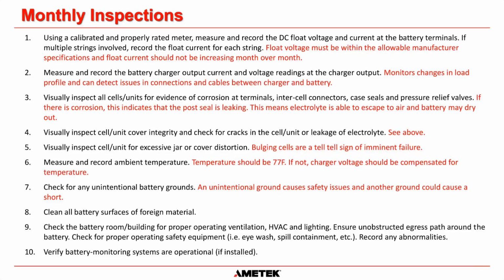So, a lot of people say that it should be 2.25 volts per cell for a lead acid battery. And that's not correct. As a rule of thumb, yes, it is kind of correct. But some manufacturers will say 2.23 volts per cell. Some manufacturers will say 2.27 volts per cell. And if you don't charge your batteries at the correct voltage, then for valve regulated batteries, if they're overcharged, you're reducing the life of your battery. And if you undercharge any battery, then you are allowing sulfation to start, and you will lose capacity in that battery. So you have to follow the manufacturer's guidelines for what the battery should be float charged at.